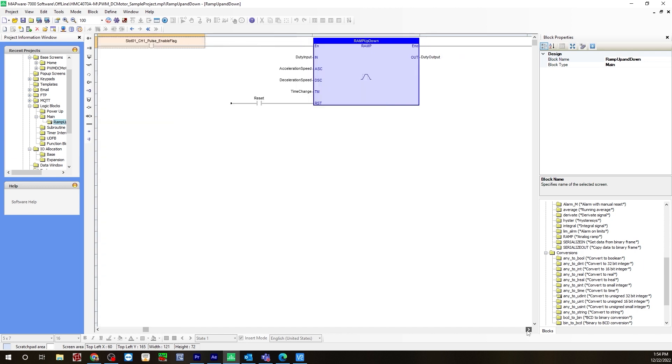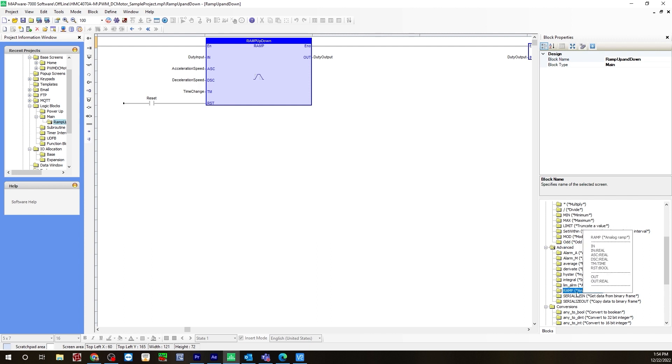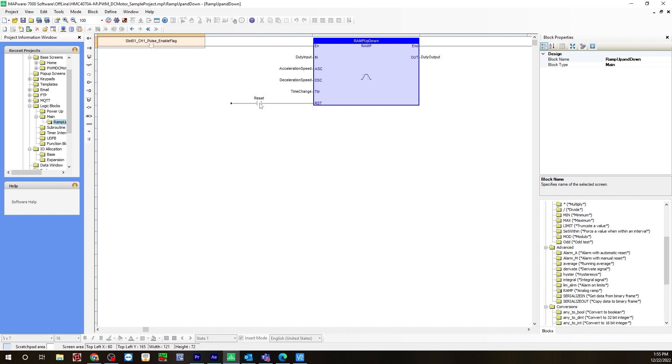The next piece of logic I'm using is a ramp function. On the right under the advanced folder, select analog ramp, drag that over to rung one after the pulse enable flag. For the input, I'm using that duty cycle input tag I created. The ascend is acceleration speed, descend is deceleration speed, and time change for time. The reset bool will go where the reset button is, and for the duty cycle output, the duty output tag we created.